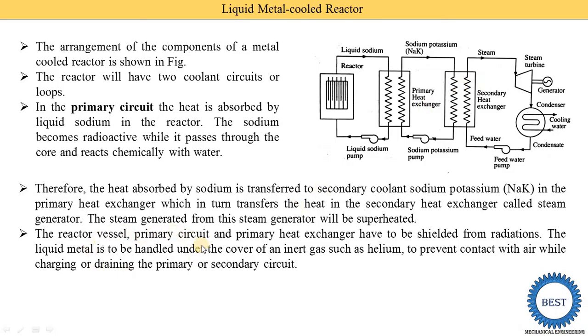The reactor vessel, primary circuit, and primary heat exchanger must be shielded from radiation, as the fuel and the sodium coolant passing through the reactor are radioactive materials. Additionally, liquid metals must be handled under cover of an inert gas such as helium to prevent contact with air when charging or draining the primary or secondary circuits.